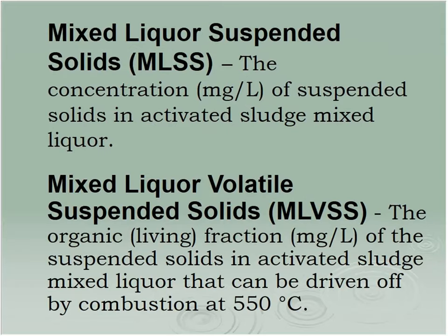We also have mixed liquor volatile suspended solids, or MLVSS. Remember, of the dry matter of our organisms, 90% is organic. Well, that's what we're looking at here. Volatile suspended solids indicates the living portion of those mixed liquor solids. Mixed liquor solids could be dead bugs, they could be little bits of who knows what, just debris. But this indicates the living portion. That's who's doing the work for you.